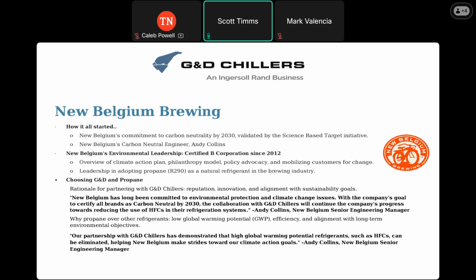A couple refrigerants ago was R404, and I want to say the global warming potential of that is around 4,500 — so 4,500 times worse from a global warming standpoint than a pound of CO2. So we were pushed to have a lower global warming potential within the industry, and we moved to R448A. Then we were pushed again, so now after R448A, essentially all of the main refrigerants, especially in the industries people here would be interested in, are called A2L refrigerants, which just means they're very lightly flammable.